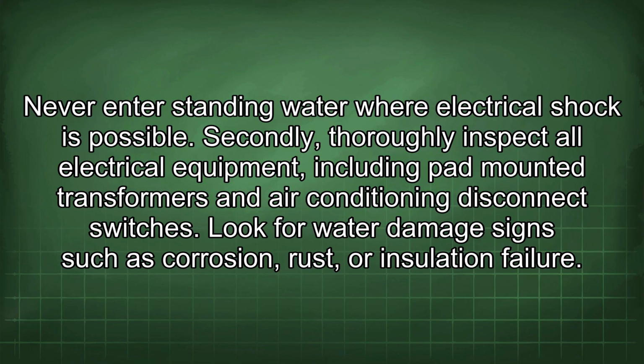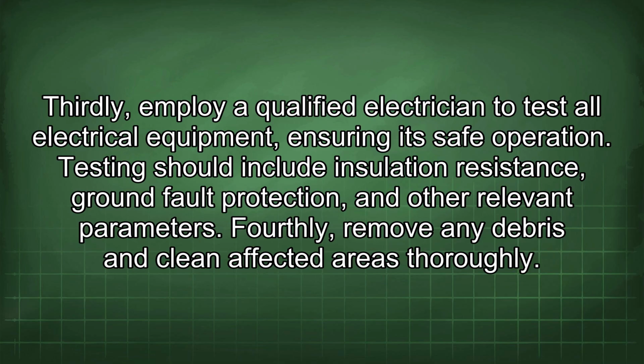Secondly, thoroughly inspect all electrical equipment, including pad-mounted transformers and air conditioning disconnect switches. Look for water damage signs such as corrosion, rust, or insulation failure. Thirdly, employ a qualified electrician to test all electrical equipment, ensuring its safe operation. Testing should include insulation resistance, ground fault protection, and other relevant parameters.